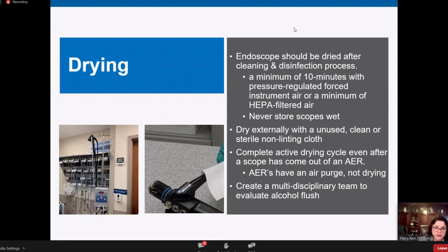So the standard says using a clean, single use, either clean or sterile, because some of the scope manufacturers' IFUs do say sterile. We stop short of requiring sterile, but we say clean or sterile, single use, non-linting cloth to dry externally, and whatever else your endoscope manufacturer says. Sometimes they tell you to dry out the valve housings or around the forceps elevator. So of course you would want to do all of that too.